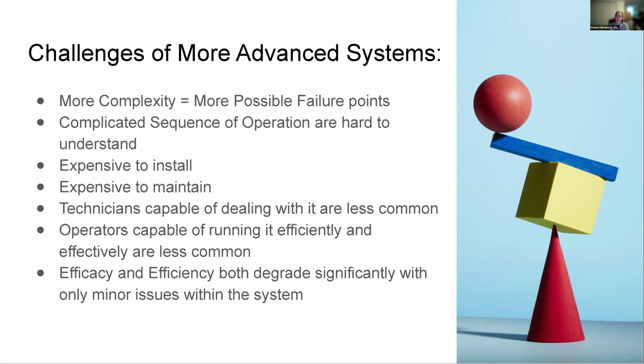We get complicated sequences of operation, particularly with our HVAC equipment, as we move from dealing with occupied and unoccupied mode to include things like occupied standby. Also, our more advanced dynamic reset schedules, whereas before, if it was 50 degrees outside, you got 60-degree air. Now we're actually looking at the loads within the zones to figure out what air temperatures we need.